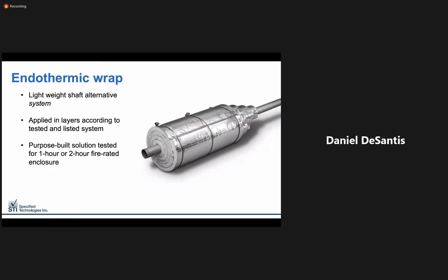The third method of protection we'll be discussing is the use of an endothermic wrap, or EWRAP for short. EWRAP is not just a material, but a tested and listed shaft enclosure system. It is a purpose-built product that was designed for the fire protection of building services. EWRAP is applied in layers corresponding to the required hourly fire resistance rating.